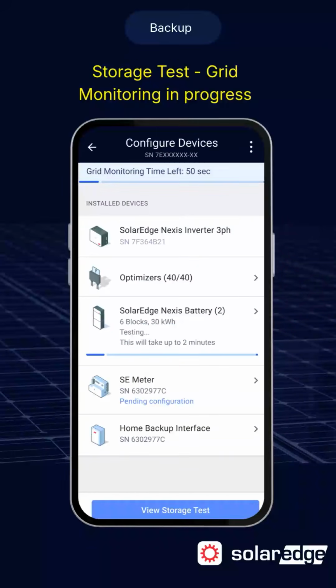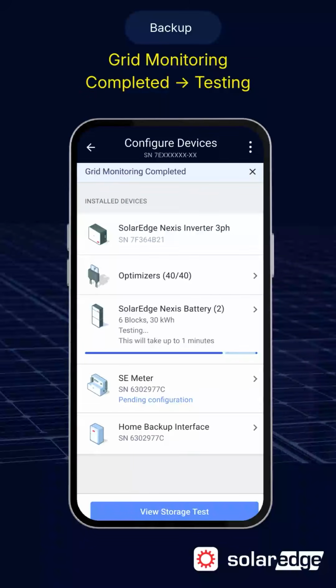The storage test is now in progress. SolarEdge Go is performing grid monitoring and verifying battery operation before backup commissioning can continue. You can monitor the test progress on screen while the storage test completes. Grid monitoring is now complete, and the storage test continues. SolarEdge Go verifies battery communication, protection, and system operation. Wait until the storage test is complete before continuing.